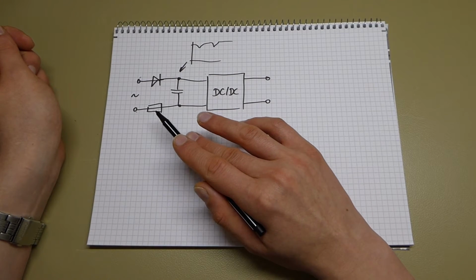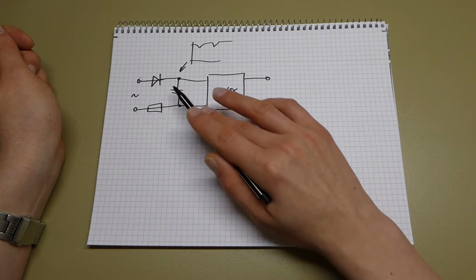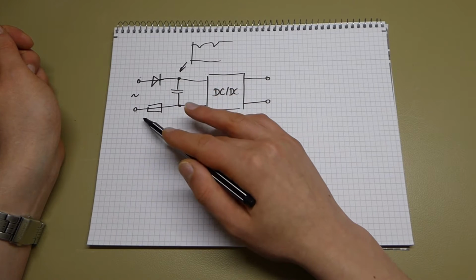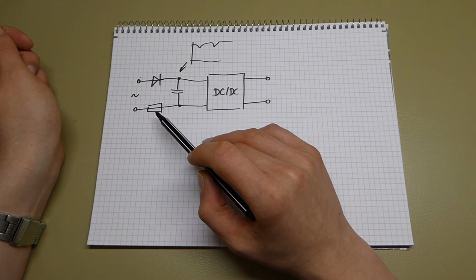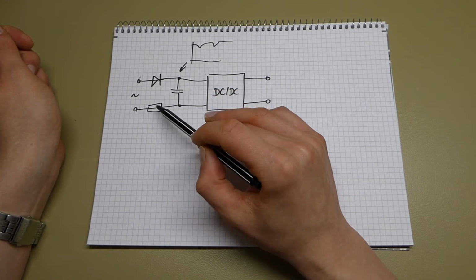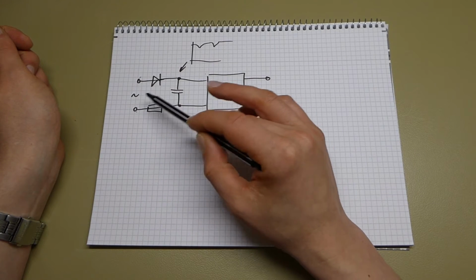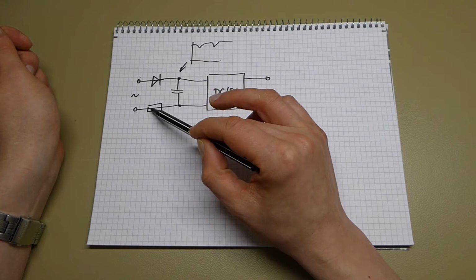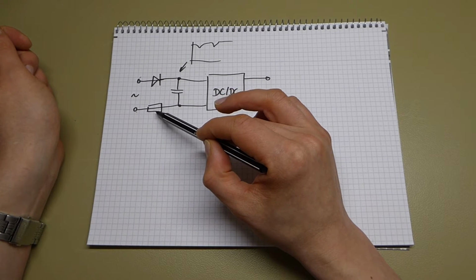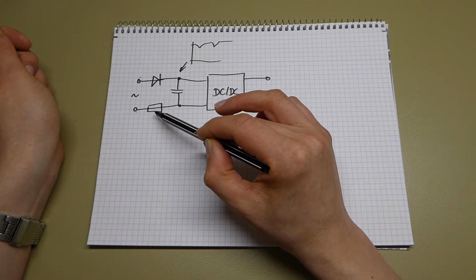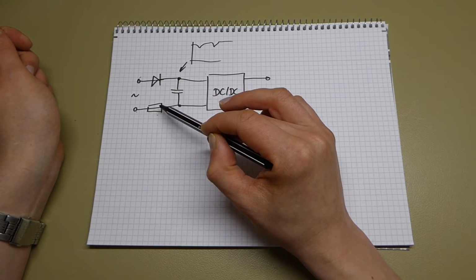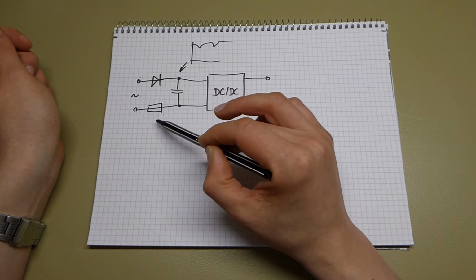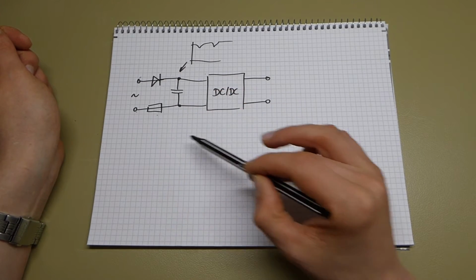The problem is that fuses rated for, say, 250 volt AC and a few amps might not actually be capable of breaking the same kind of DC current, because DC currents are much more prone to creating arcs inside the fuse. So your normal little glass type fuse might not be capable there.